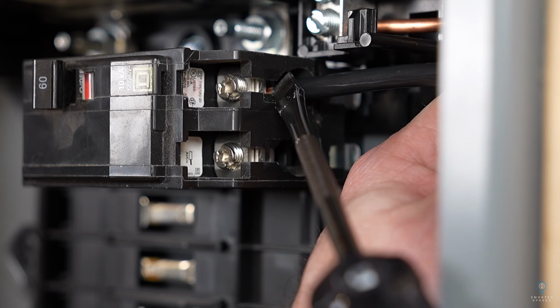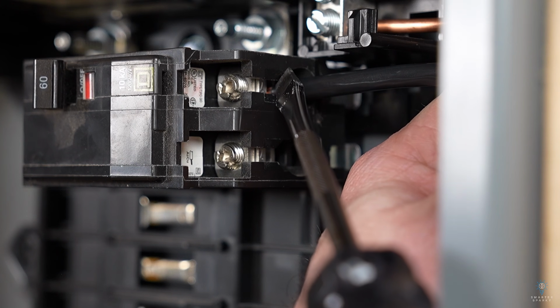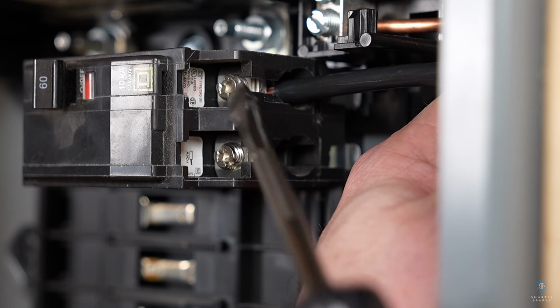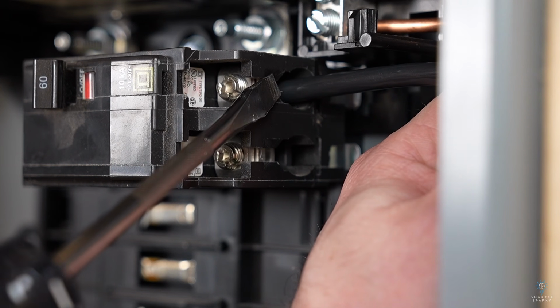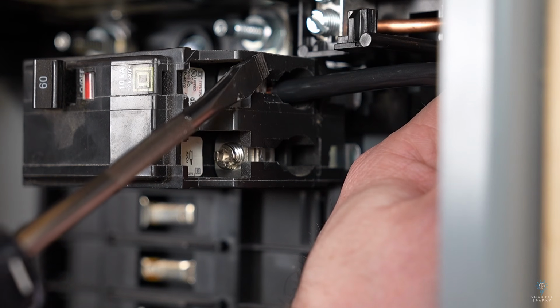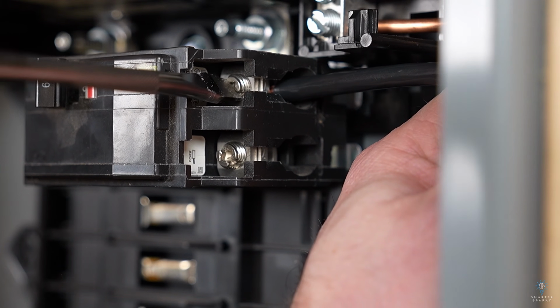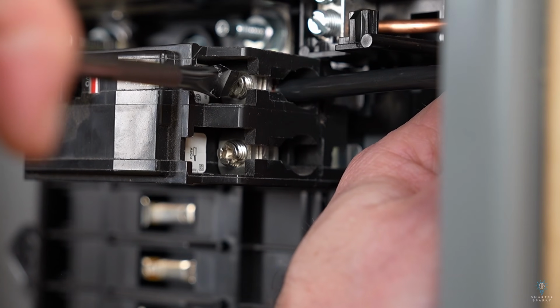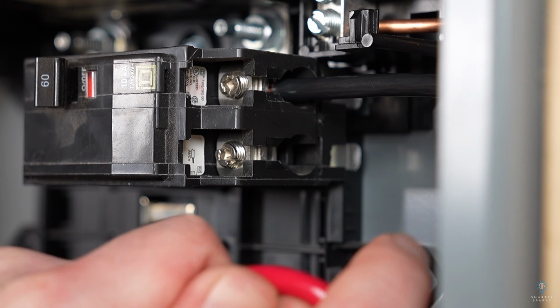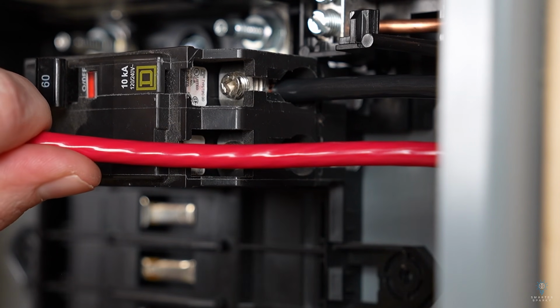Notice how we can see just a little bit of copper on the outside of the metal part of the breaker, but we don't see any copper leaving the back side of the breaker here. So we can go ahead and tighten that lug down. And that one is good. And now we can install our second line here.